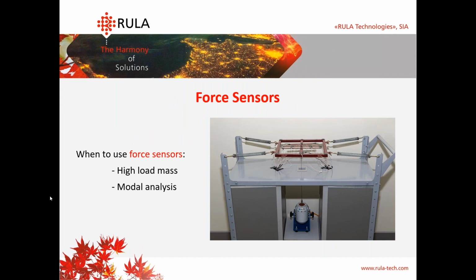In our software, we also can connect force sensors. They can be used when we have a high load mass or in modal analysis. Here on the right side, you can see our modal analysis object. It is a metal frame with 4 springs. And here on the bottom, we have a force sensor connected with our shaker. It can be applied really nicely here, because when we run, for example, a random test and get impact with a force sensor, it can be really good applied in modal analysis. So the main use of force sensors is modal analysis with multi-shaker tests, for example, random.